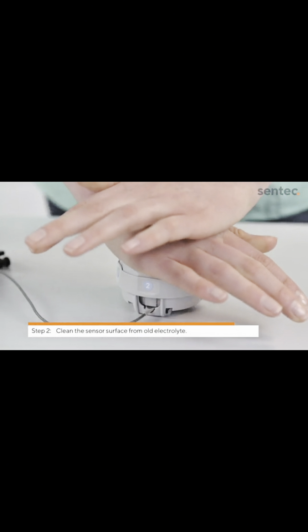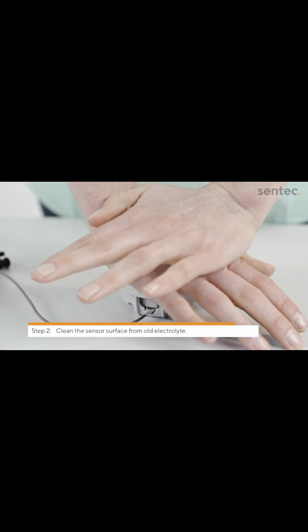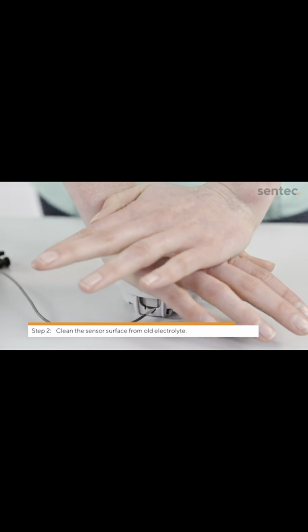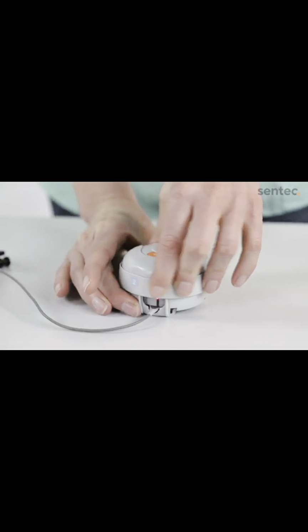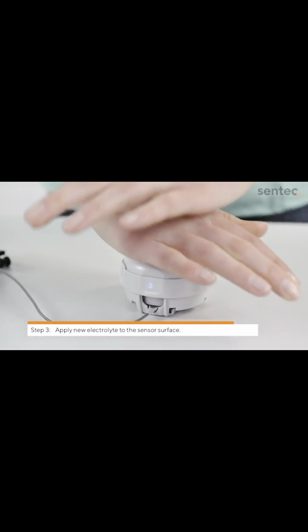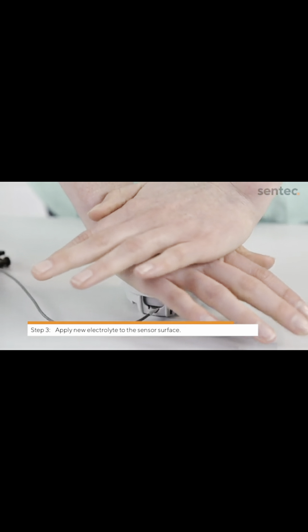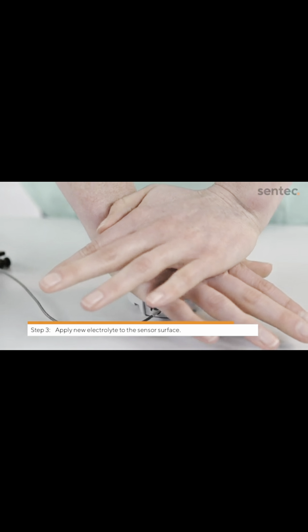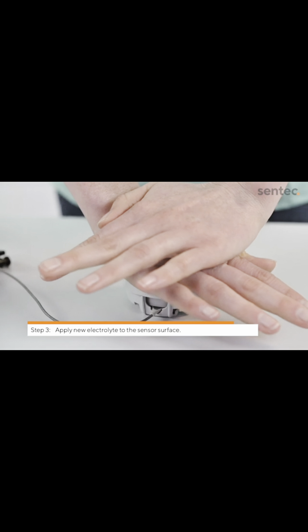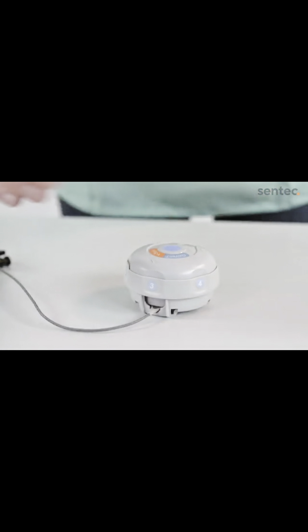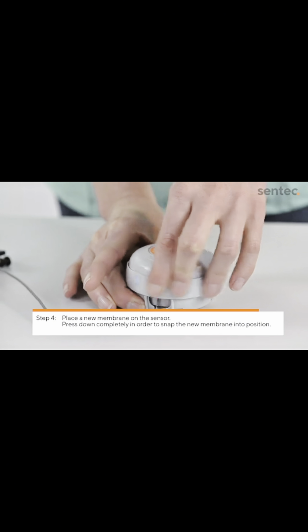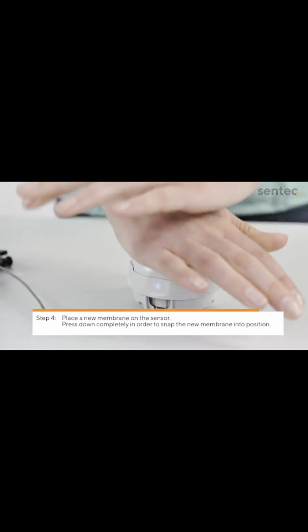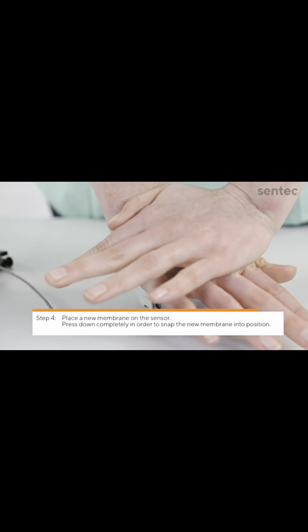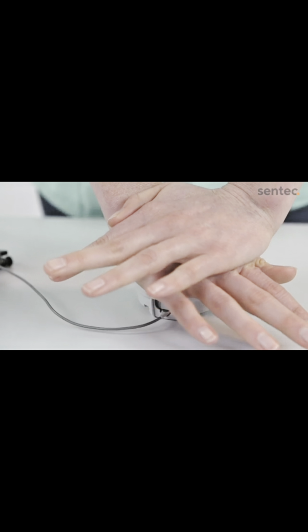Repeat this process in step 2. Press slowly but firmly. Gently release the top and then turn to the next step. And again in step 3 to release the electrolyte, which is signaled by a pop sound. When you reach step 4, make sure to press down completely in order to snap the new membrane into position. This is easiest if you stand and press with both hands.